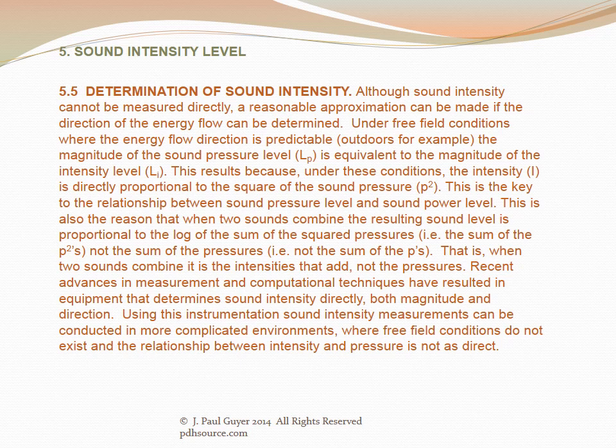When two sounds combine, it is the intensities that add, not the pressures — that is, the resulting sound level is proportional to the log of the sum of the squared pressures (p²), not the sum of the pressures. Recent advances in measurement and computational techniques have resulted in equipment that determines sound intensity directly, both in magnitude and direction, allowing measurements in complicated environments where free field conditions do not exist.